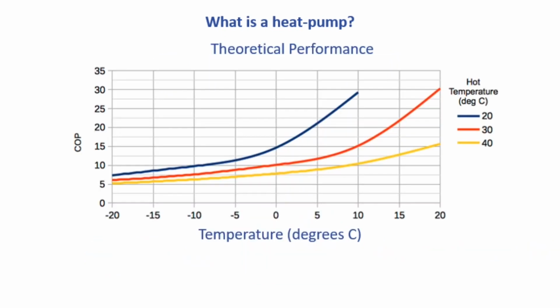So theoretically, using this formula that we saw on the right-hand side of the previous slide, we can plot these lines which show the maximum theoretical coefficient of performance for different temperatures. So if we were trying to dispatch heat at 40 degrees and we had an outdoor temperature of, let's say, 10 degrees, theoretically we could get a coefficient of performance as high as 10. So in other words, for every unit of electricity that goes into our system, we can shift 10 units of heat with our conveyor belt. And if the temperature outdoors goes down, the coefficient of performance theoretically drops, and it also rises the higher the ambient conditions are. The closer the ambient temperature is to the temperature you want to dispatch heat to, the higher your coefficient of performance.